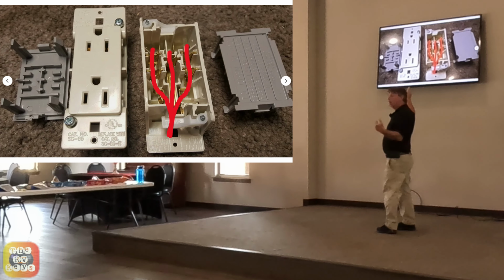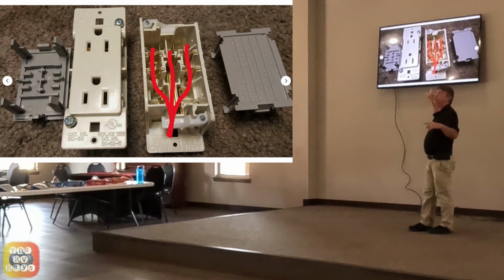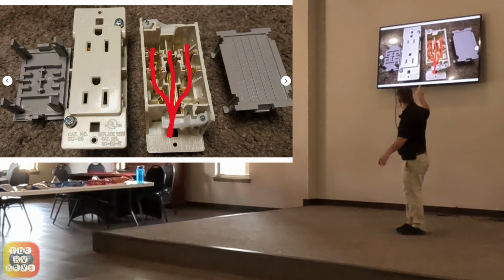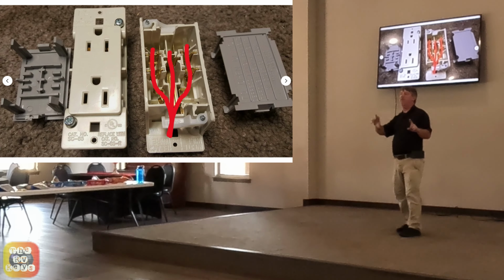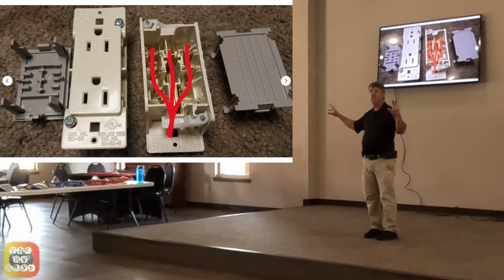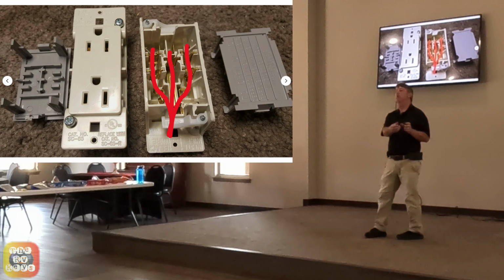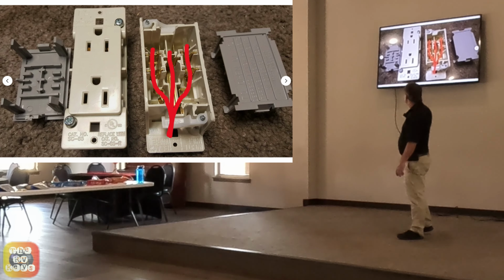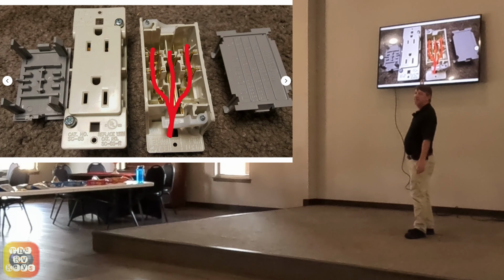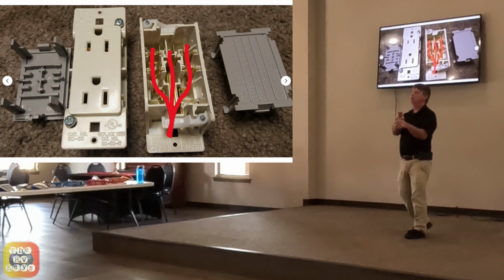The problem is, even on my own rig - we're 3.5 years now in the rig - 4 months ago we had a set of outlets fail. I went to the first outlet closest to the panel, where it was feeding it, and checked that. As I pulled it out of the wall, I heard some crackling in the outlet. They had put 3 wires into that set, and the outermost wire, the hot coming from the panel, was loose in the outlet.